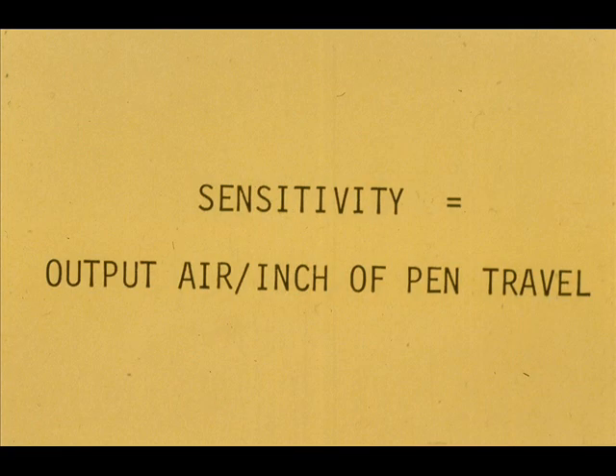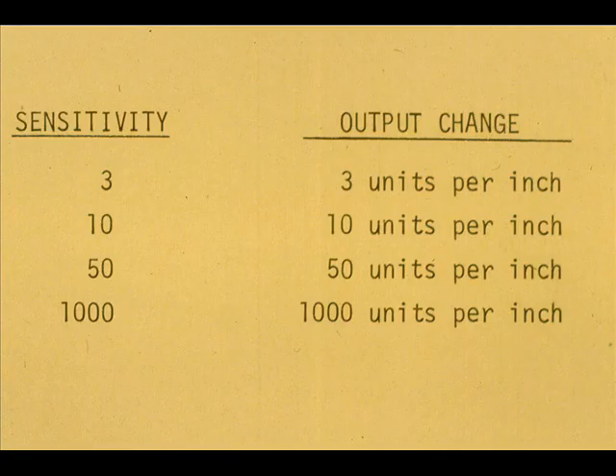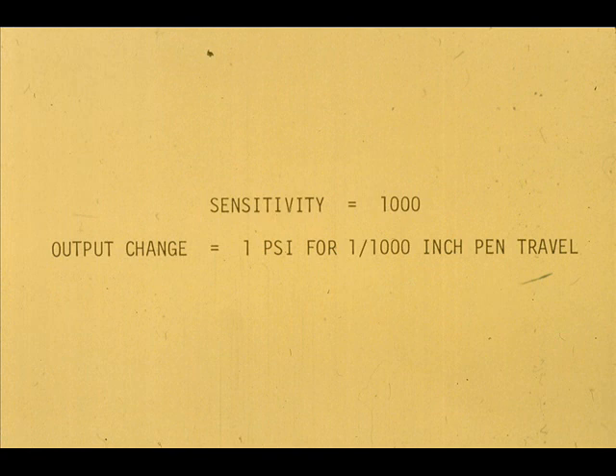Sensitivity equals the output air change per inch of pen or measurement change. A sensitivity setting of three means the output air would change three PSI for each inch of pen travel. If the sensitivity is set at 1,000, the pen only has to travel 1/1000th of an inch to change the output air one pound. For a pneumatic controller, this is practically on-off control.